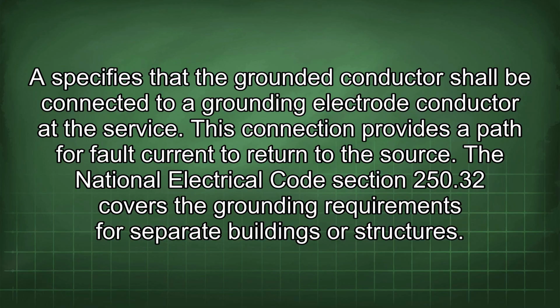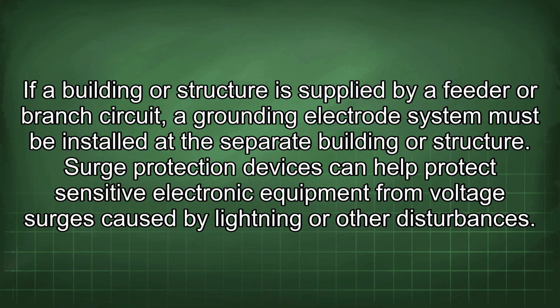The National Electrical Code Section 250.32 covers the grounding requirements for separate buildings or structures. If a building or structure is supplied by a feeder or branch circuit, a grounding electrode system must be installed at the separate building or structure.